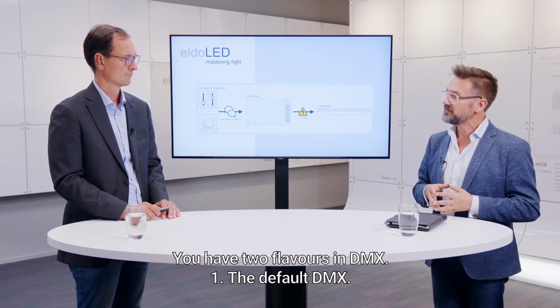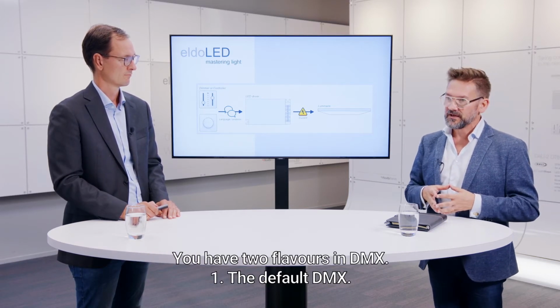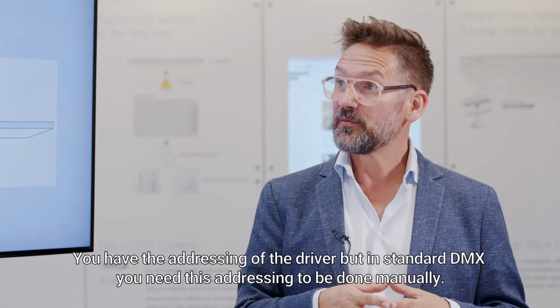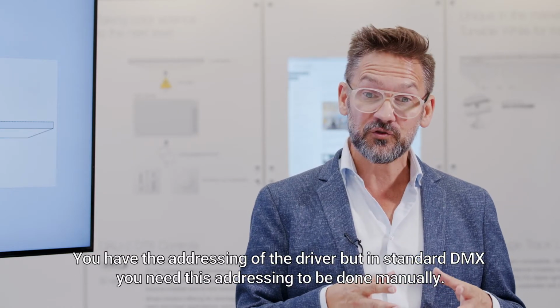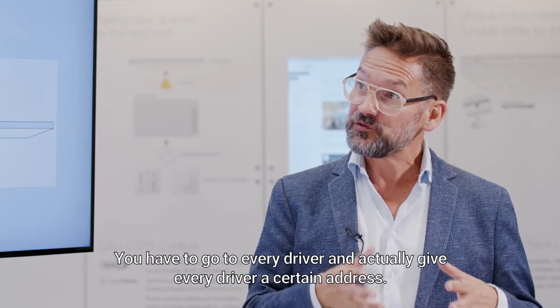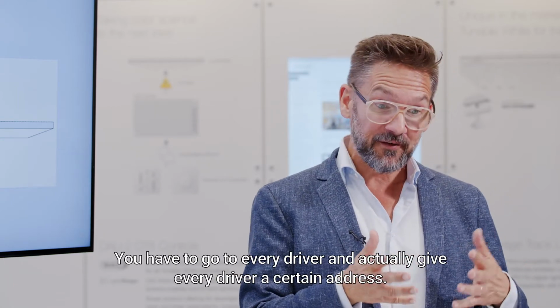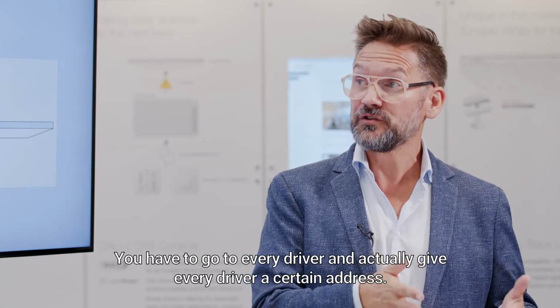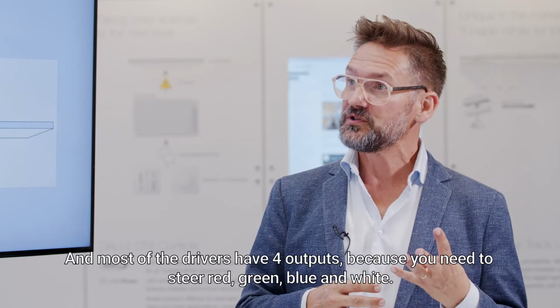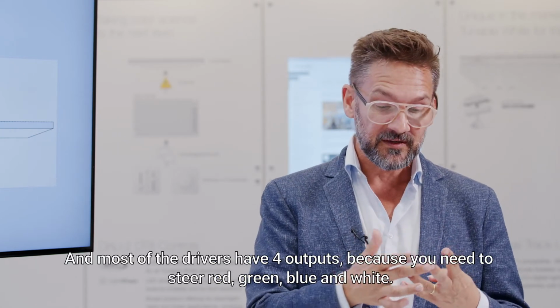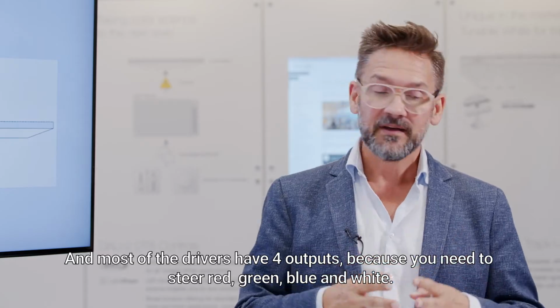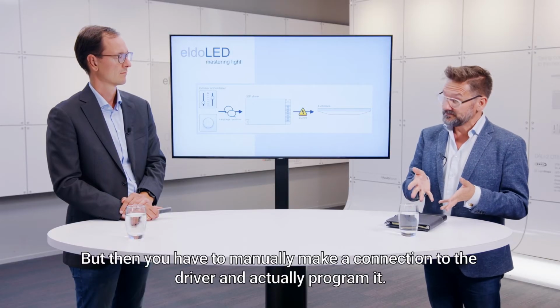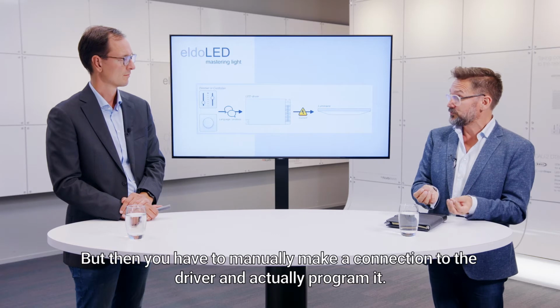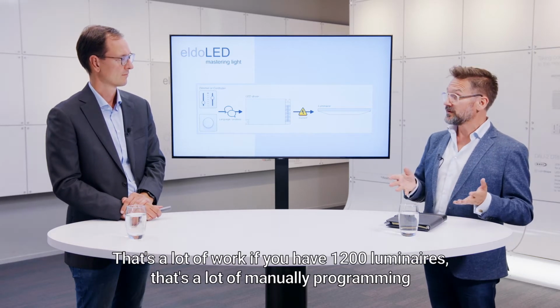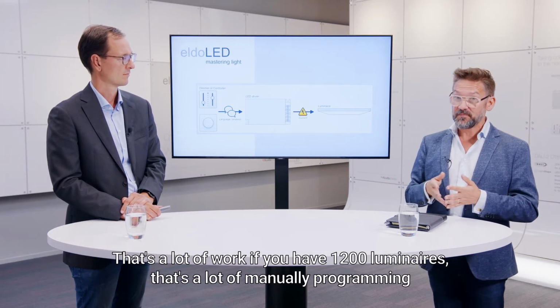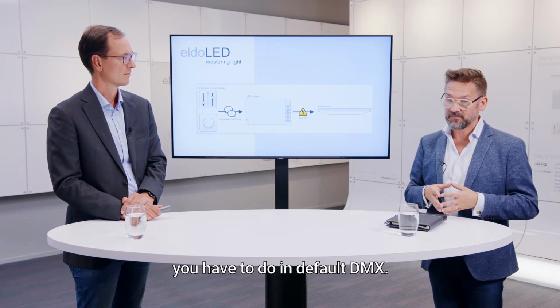You have two flavors in DMX. The default DMX, you have the addressing of the driver, but in standard DMX you need this addressing to be done manually. You have to go to every driver and actually give every driver a certain address. And most of the drivers have 4 outputs because you need to steer red, green, blue and white. But then you have to manually make a connection to the driver and actually program it. That's a lot of work. If you have 1200 luminaires, there's a lot of manual programming you have to do in default DMX.